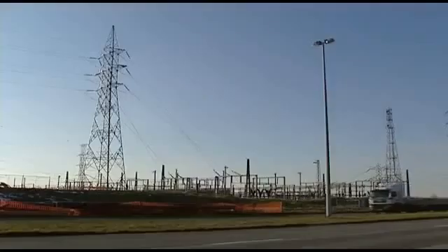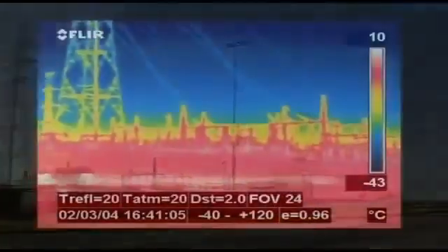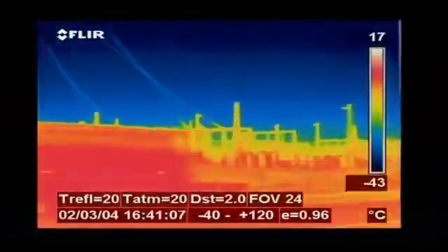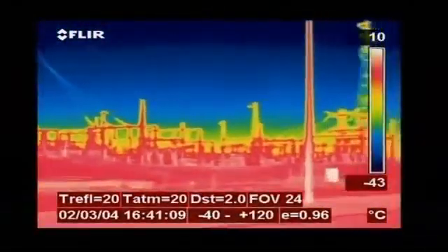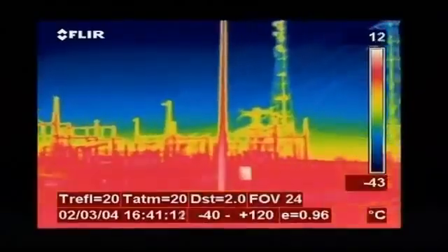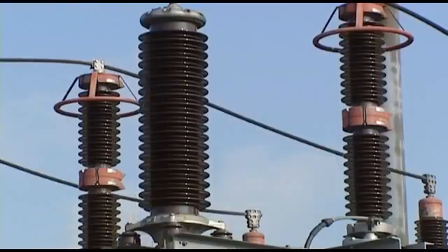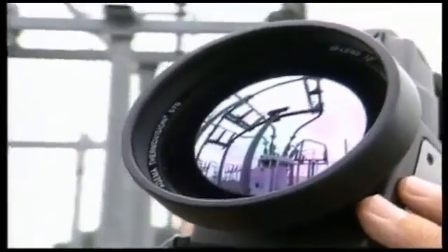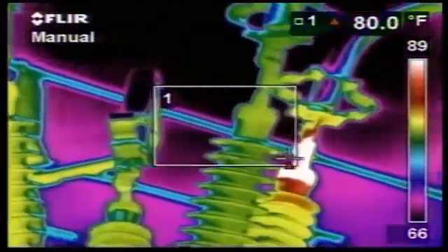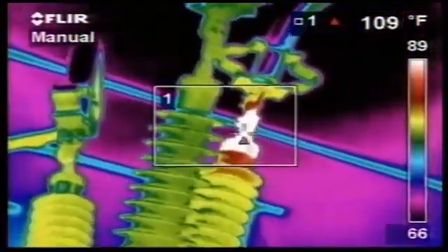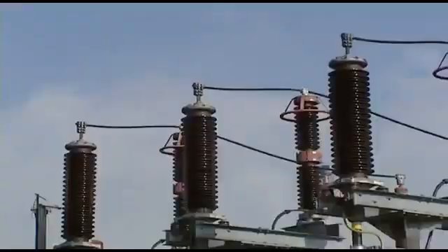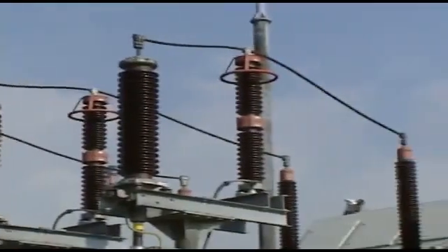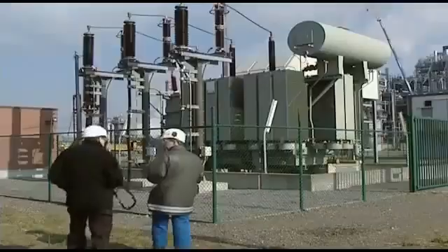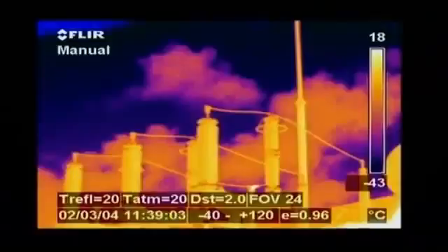Thermal imaging cameras are also commonly used for electrical high voltage inspections. As electrical connections become loose, there's a resistance to current that can cause an increase in temperature. This can then cause components to fail, resulting in unplanned outages and injuries. In addition, the efficiency of an electrical grid becomes low prior to failure. Thus, energy is spent generating heat, causing unnecessary losses.